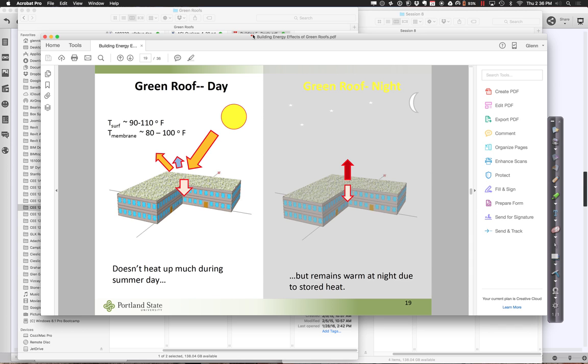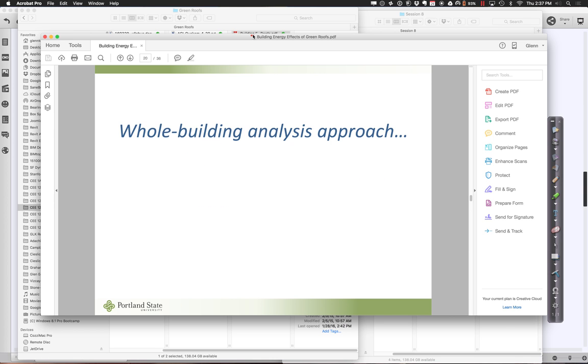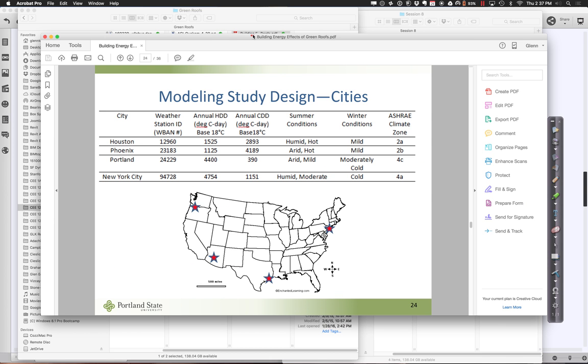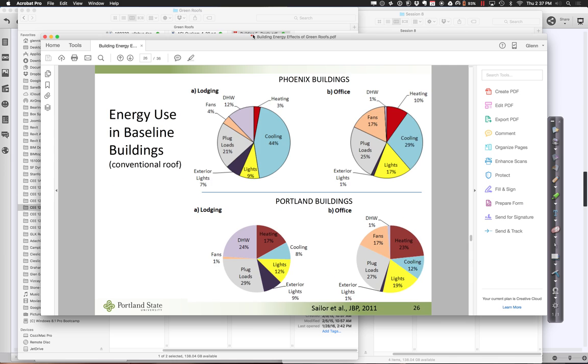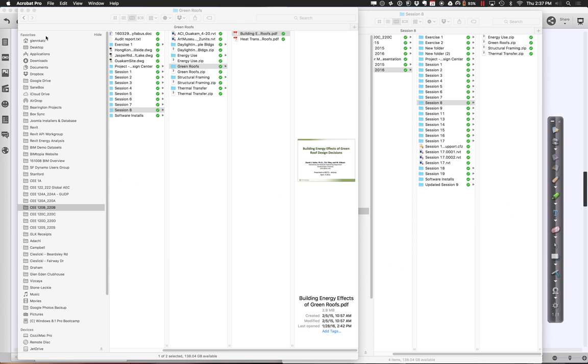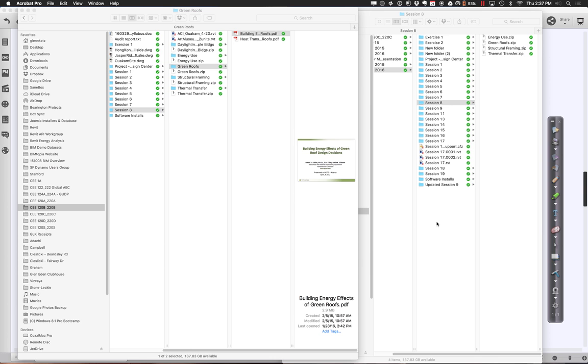That's why thermal mass is a good thing. Even here in Y2E2, we have all this concrete that's exposed. It's all about thermal mass. You want to have that and hold nice constant temperatures throughout the day. If you are thinking about green roofs, realize the reason they're so effective isn't necessarily just the thickness in terms of the conductive value. It's actually thermal mass. Even if you put that in the red, you'll see that as you add layers of earth, it creates quite a bit of thermal mass which is very good at storing heat or cool. The biggest thermal mass we have is the earth. That's why it holds such a nice constant temperature. Even though it changes at the surface, below the surface it doesn't swing very widely at all.